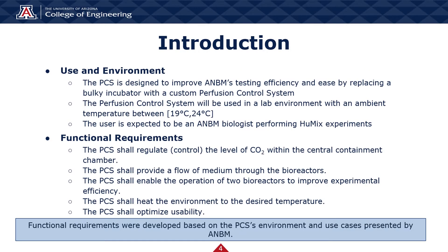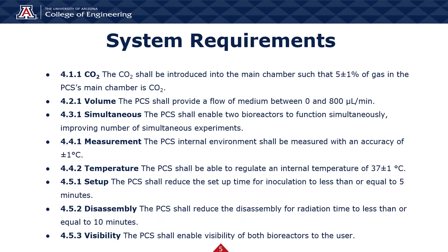To design such a product, it was crucial that the functionalities presented in the incubator were still available. Functionality such as thermal control and CO2 concentration control was vital for the PCS. On account of the system being designed to operate in ANBM's facility, which is kept at approximately 21 degrees Celsius, environmental performance was also a factor. Our sponsor emphasized the difficulty biologists have had performing Humix experiments and wanted the PCS to allow easy access to materials inside, as well as the ability to view the bioreactor without disturbing the cell environment. After initial meetings, our team settled on the functional requirements displayed on screen, which were quantified into single, verifiable shall statements — the system requirements for the PCS listed on this slide.